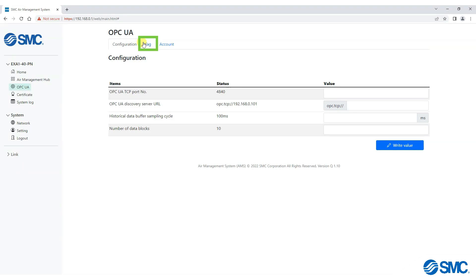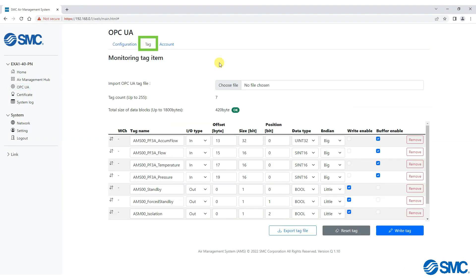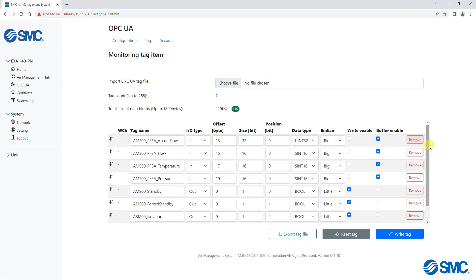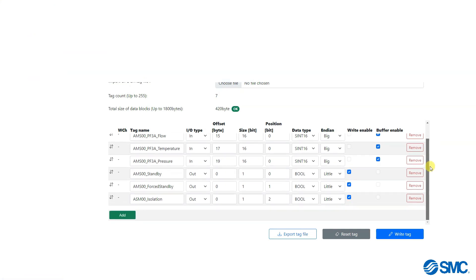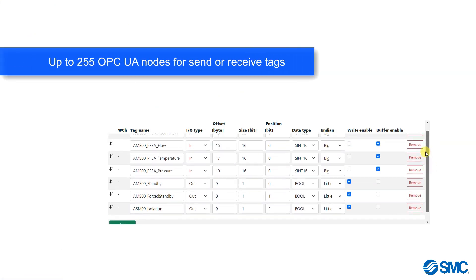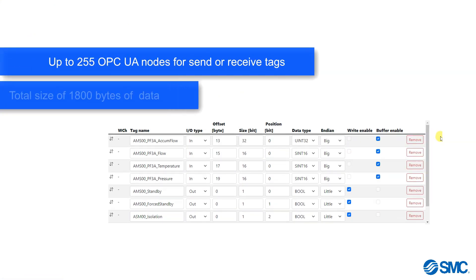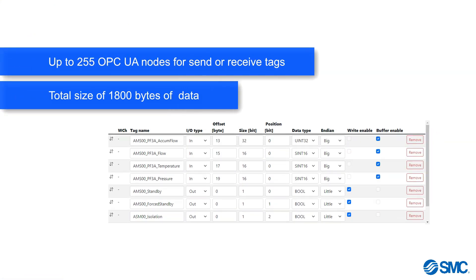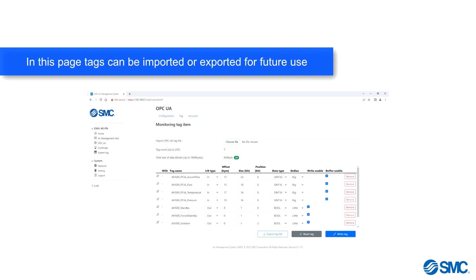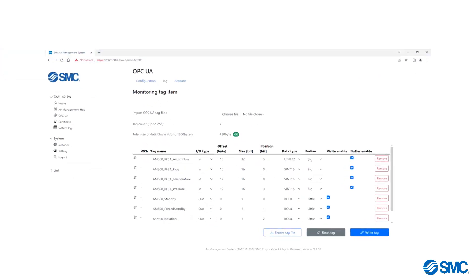In the Tag tab, the OPC UA nodes can be configured to send and receive up to 255 tags. An adjustable data buffer is available for up to 1800 bytes of data. It is possible to import and export tags here in order to store or save them for future use.